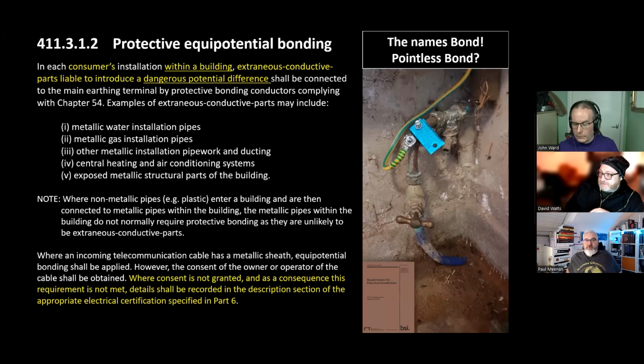Yesterday morning. And they spoke about this, which is one of the reasons why I highlighted it, because listening to your peers is always a good thing. For me, potential difference is just voltage difference, which is what equipotential bonding is for. Dangerous, in my opinion, is a dangerous term, because what you're now doing is saying I can tolerate certain voltages. If you look at G12, I'm going to use railways as an example. G12 doesn't allow a touch voltage on railways above 25 volts. And there's a reason behind that. I don't know what dangerous is. I am assuming that there is something in a new guidance note that's yet to come. So we'll probably cover this in a future podcast.